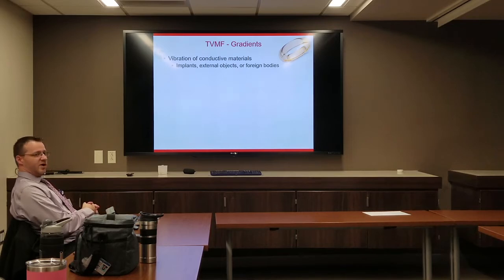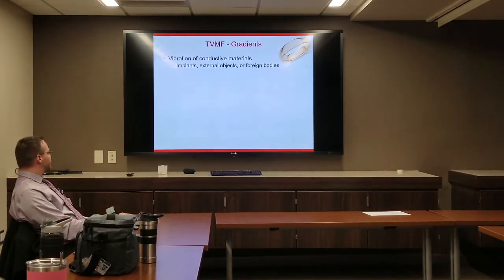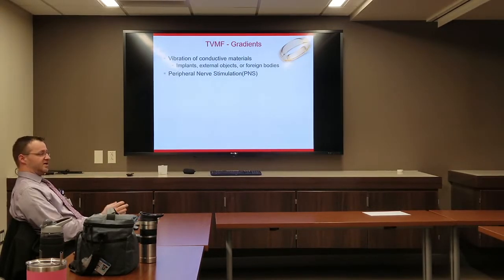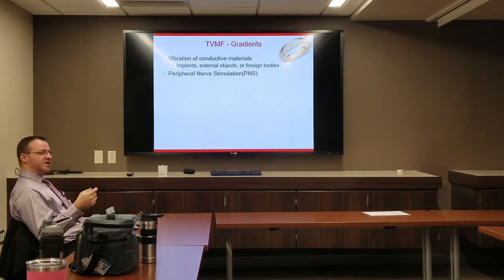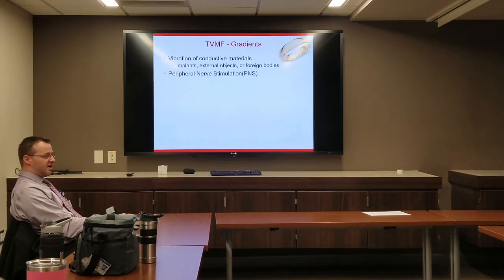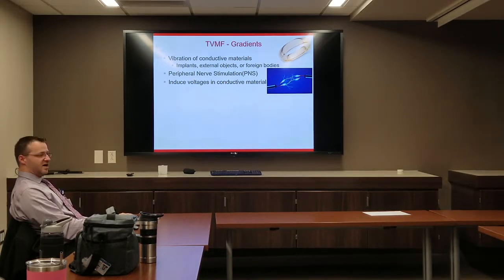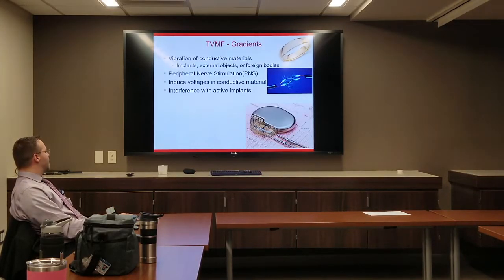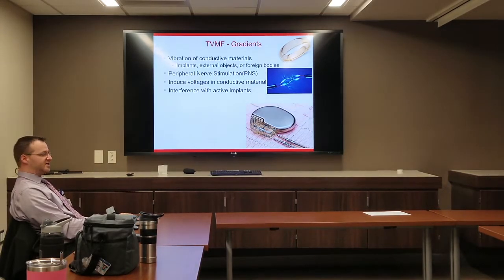The time-varying magnetic field from gradients causes vibration of conductive materials — implants, external objects, or foreign bodies. This is also the cause of peripheral nerve stimulation. Patients may experience inadvertent muscle contractions — for example, a muscle spasm in the forehead during chest or abdomen imaging sequences. It can also induce voltages in conductive materials, which is why we need to know about implants before placing people in the scanner. It can interfere with active implants such as stimulators, pacemakers, and ICDs.